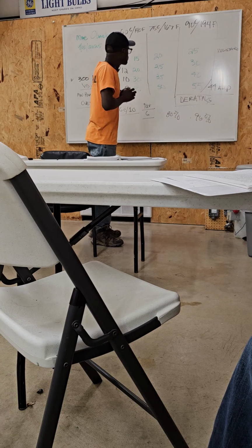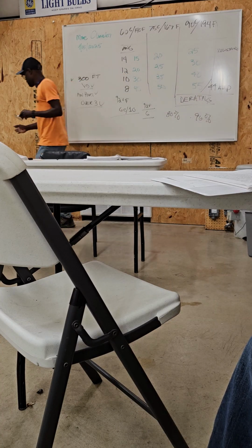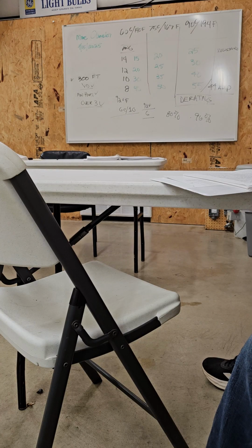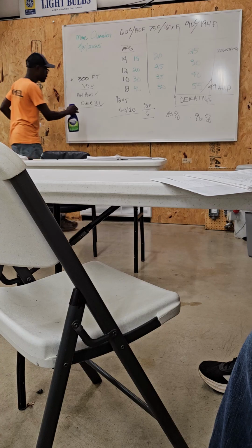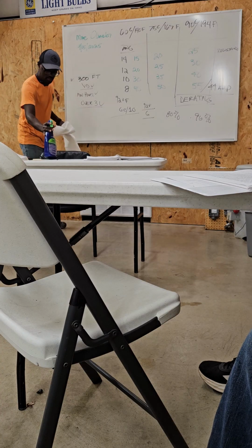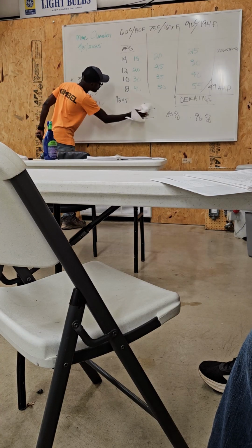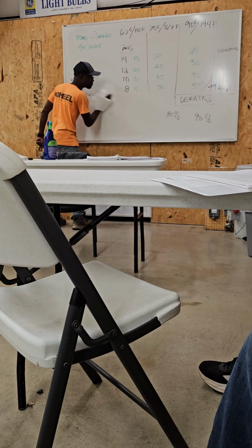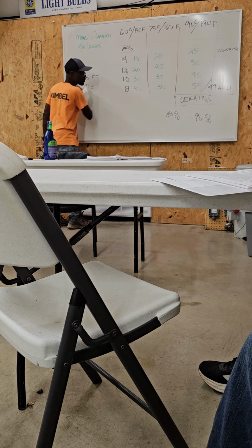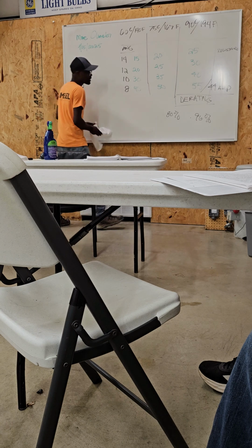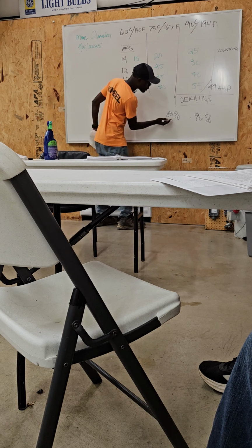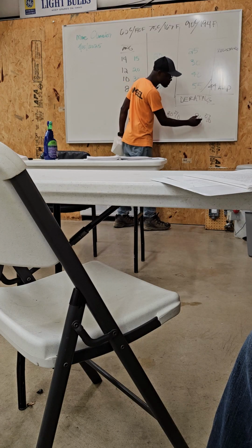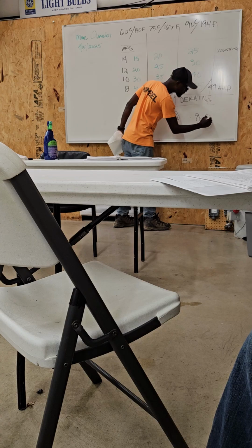Now, here's what you do. This is what I don't want you guys to get lost. Please, whatever you do, don't get lost. We're gonna do a bunch of those. Trust me. If you haven't done a lot of those, don't worry. So now I have 2 numbers. It is 80% because I have between 4 to 6 conductors, and it is 96% because of what? Because of my temperature.